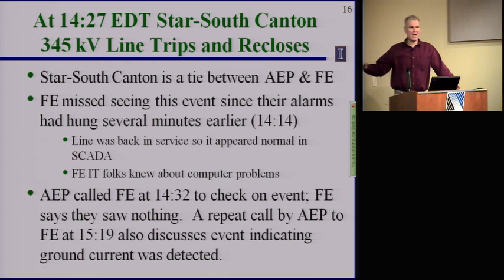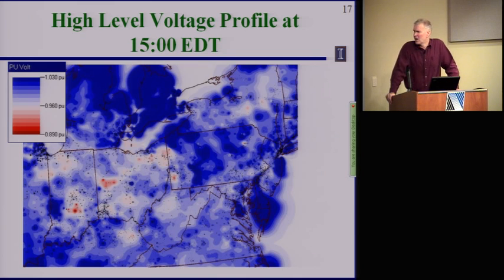So these guys were working on it, but they didn't tell the operators. At the same time, the operators were getting calls from their neighbor AEP, which owned the far end of the line, saying, hey, we had a trip and reclose on this. First Energy said they didn't see anything, and the reason is their alarms hung. There are actually recordings of these phone calls, from American Electric Power, though I guess they've never been made public, discussing that this was a very unusual event. So they sort of knew something was going on, but it didn't affect them. At least they were still thinking it was a good day.